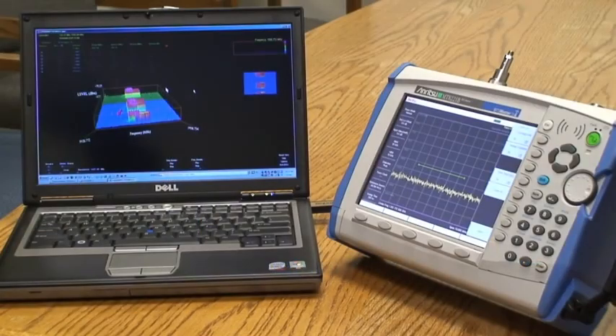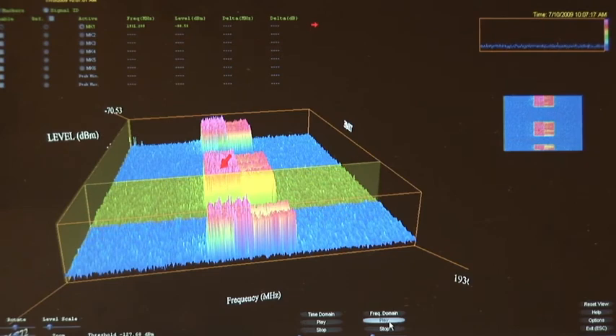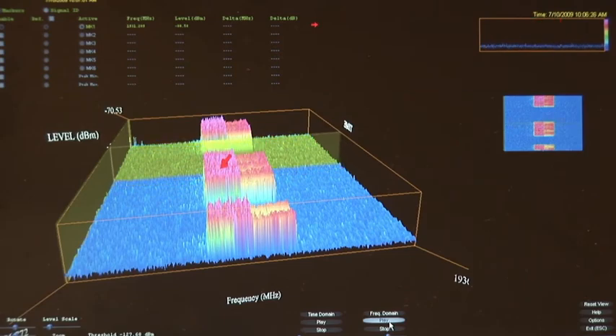To see small intermittent interferers clearly, you can use the 3D Spectrogram which integrates both color and the spectrum analyzer in one view, highlighting single interfering signals which don't last more than one sweep of the spectrum analyzer.